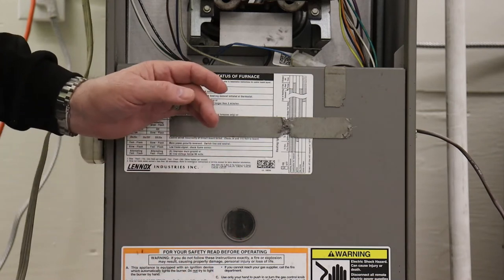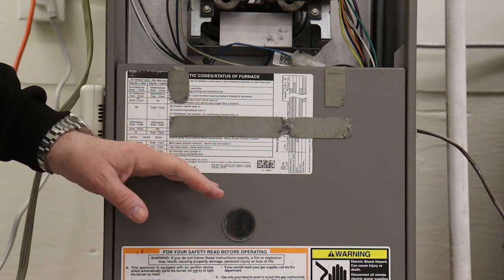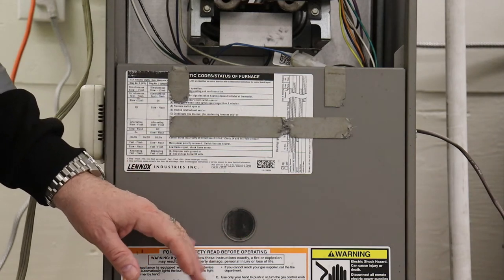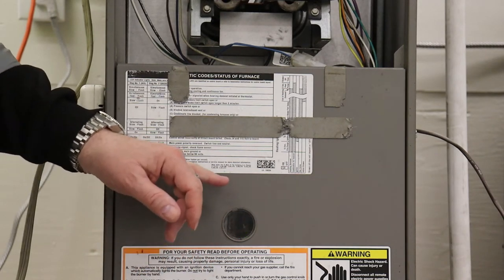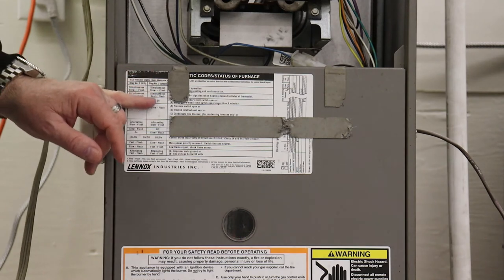Because once you remove the door, you kill the power on that board and it's going to erase any codes. You want to look at it first, then write those down so you can check them off of the board's fault code chart.